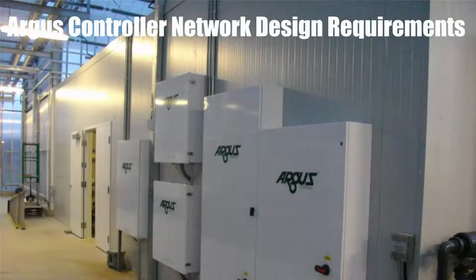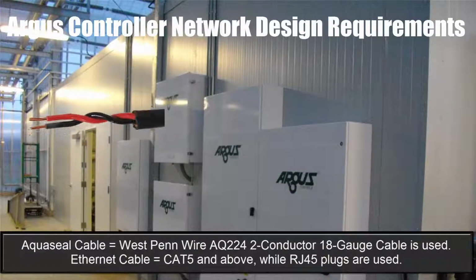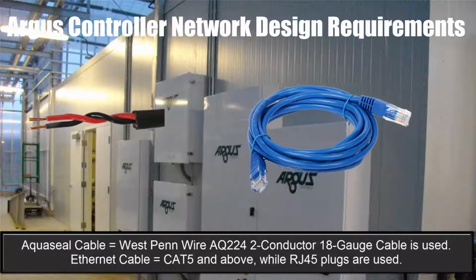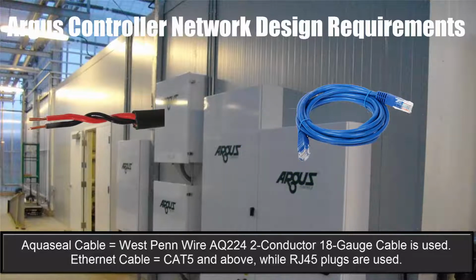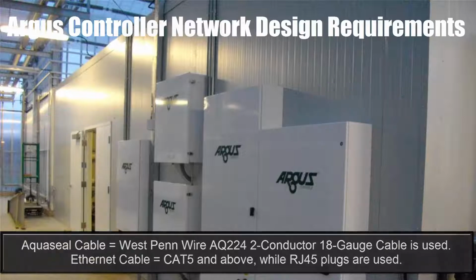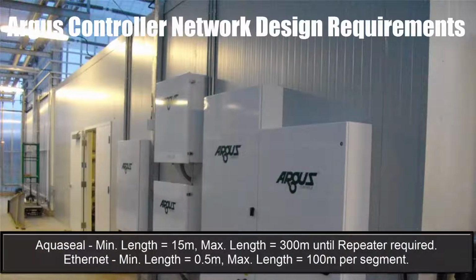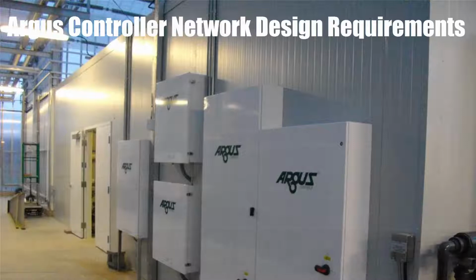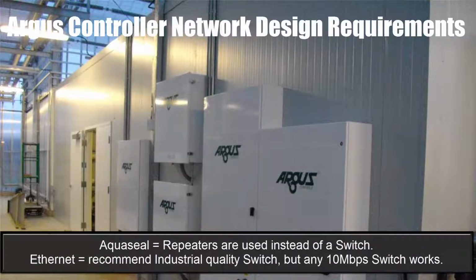Network design requirements. For Aquaseal cabling, a West Penn Wire AQ224 2-conductor 18-gauge cable is used. For Ethernet, cable type is Cat5 and above, while RJ45 plugs are used. Minimum Aquaseal cable length is 15 meters, and maximum cable length is 300 meters before a repeater is required. The minimum Ethernet cable length is 0.5 meters, and the maximum cable length for Ethernet is 100 meters for a segment. For Aquaseal cable, repeaters are used instead of a switch.